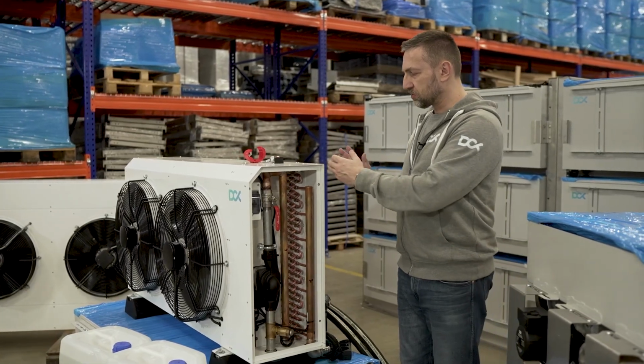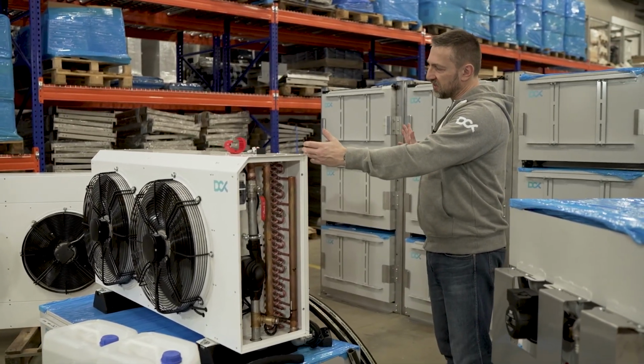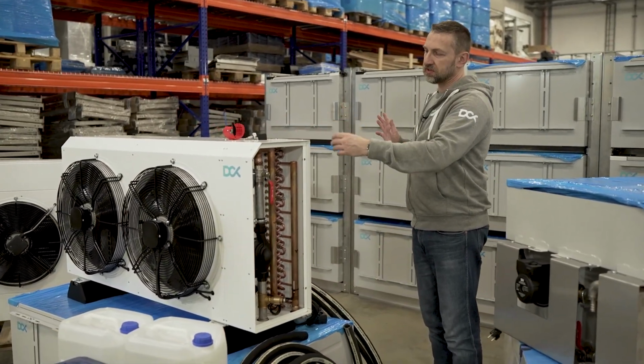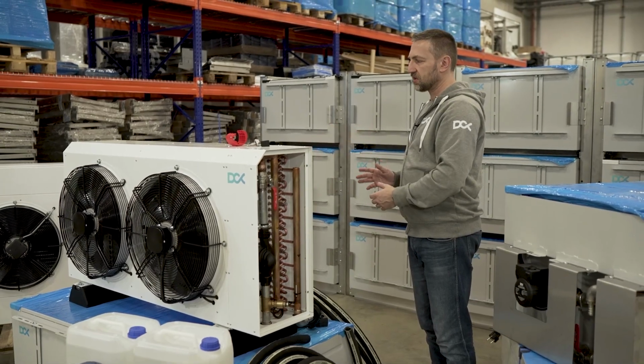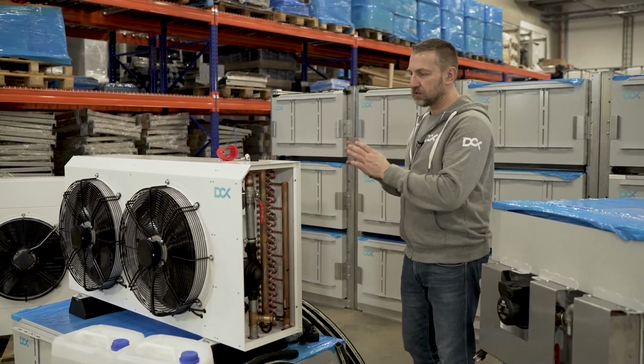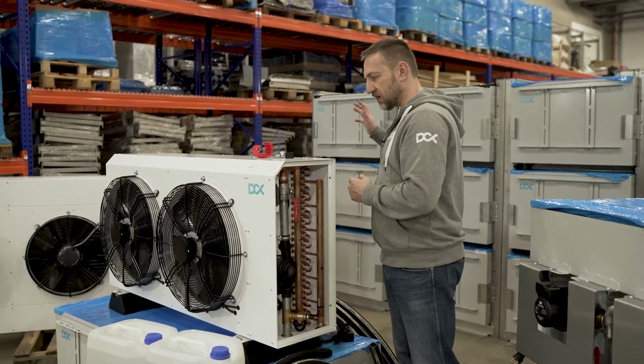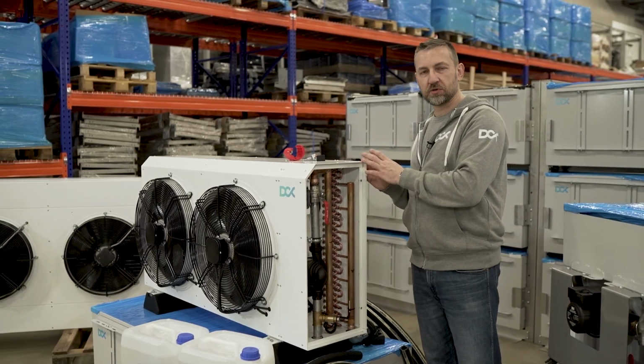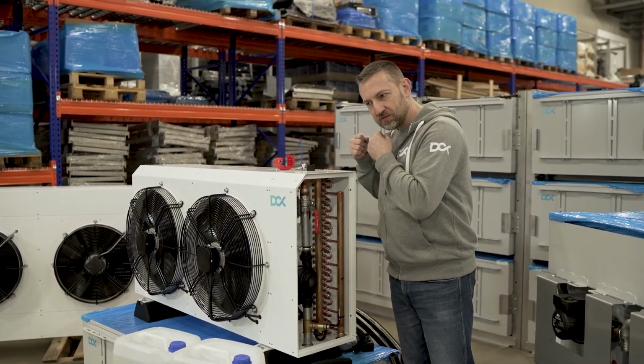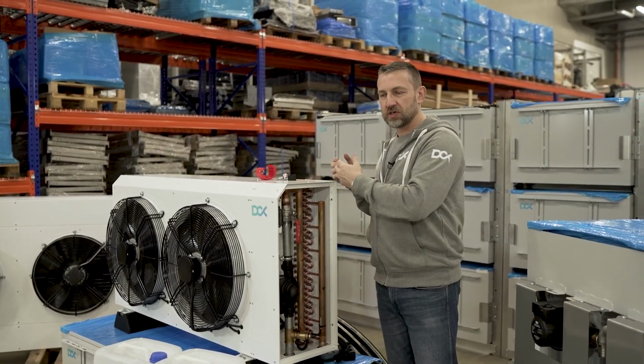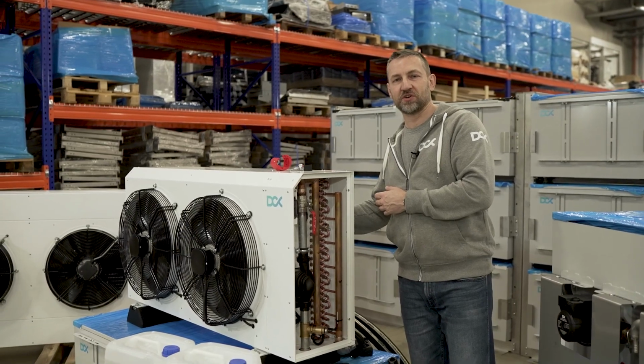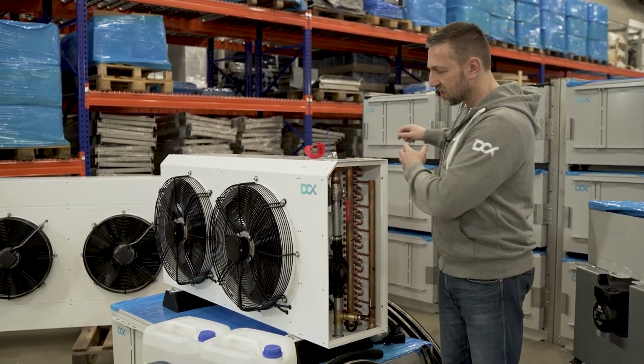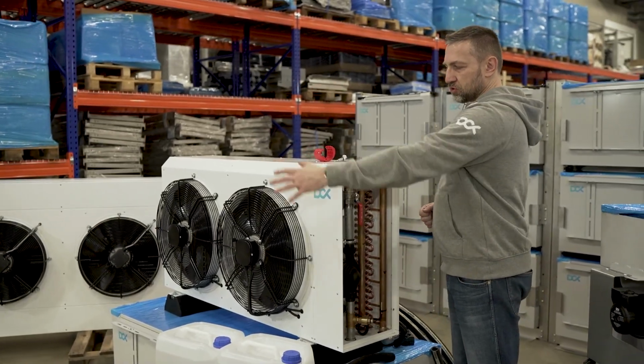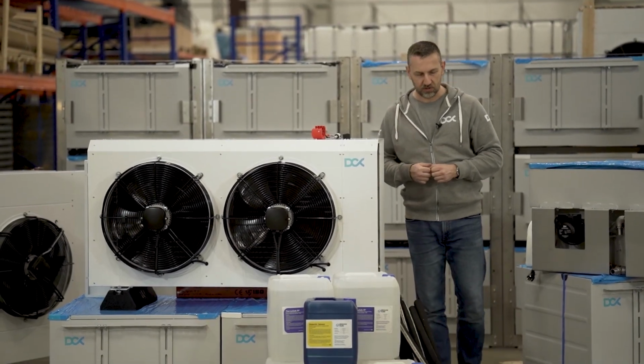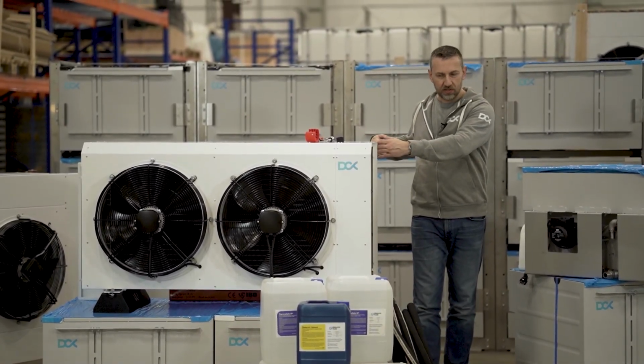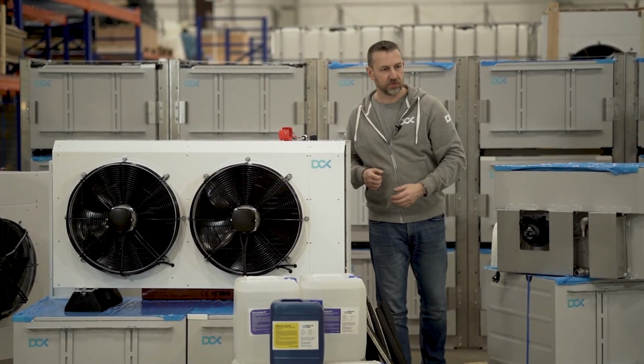The unit must be located with some space from the wall, ideally 1 meter. If that should be less, well, that's just fine. Just keep at least half a meter of distance so the unit can breathe. And again, it must have access to the fresh air, the outside air. It will not work inside. We saw some installations where customers are putting fans to push that flow into the compartment, but it's always sucking the fresh, colder air from the outside. The fans are sucking the air through the coils, so we should have unobstructed space here so they can operate. So keeping the proper distance on both sides of the dry cooler is pretty important.